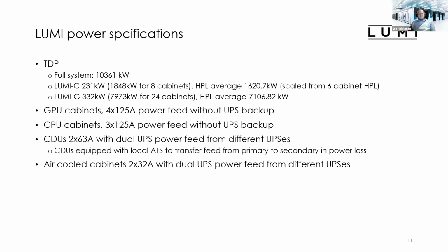Each of these GPU cabinets has 4 125 amp power feeds without UPS backup, and all the CPU cabinets have 3 power feeds of the same size without UPS backup. Those cooling units, which each cool 3 GPU or 3 CPU cabinets, have 2 by 63 amp power feeds with dual UPS power feed from different UPSs.